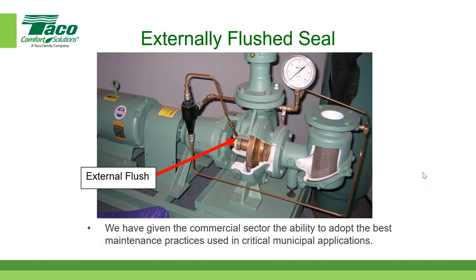So I'm going to actually, someone made a note that says that they've had experiences, not necessarily TACO, but they've had an experience where the couplers shear off periodically. And I'm going to guess and say, if there is a coupling issue that's shearing off, chances are the alignment has not been done properly. So the alignment between the motor shaft and the pump shaft has to be within 5/1000ths of an inch. And if it's more than that, and substantially more, then that would cause the flex coupling to flex more often than what it's supposed to, and it'll probably heat up and shear off. So if you're seeing a problem out there, my guess is that it's not aligned properly. Yeah, that would be my guess.